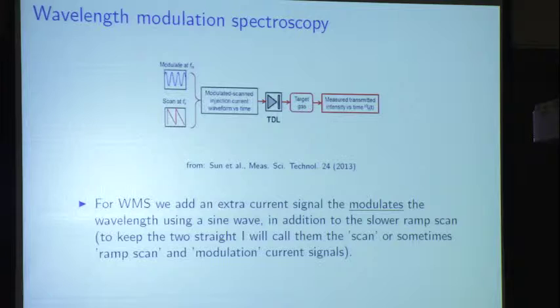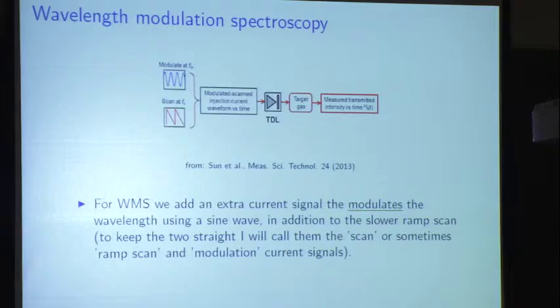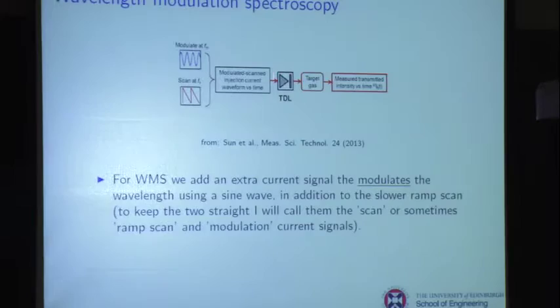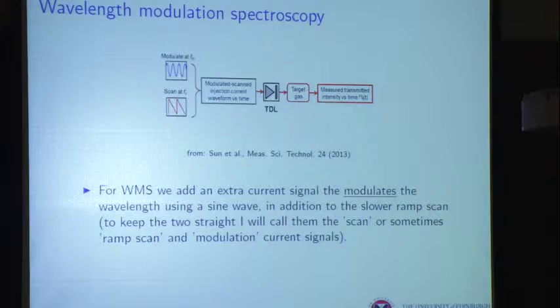For wavelength modulation spectroscopy, we add a sinusoidal current signal. We're doing two things at once to the wavelength: we slowly scan across the absorption profile, and we also modulate at high frequency but with much smaller amplitude. I'll call the slow one the scan — it goes all the way across the line — and the modulation is the small, higher-speed one. The scanning frequency FS is on the order of tens of Hertz; the modulation frequency FM should be in the range of 10 kHz into the megahertz to avoid 1/f laser noise.